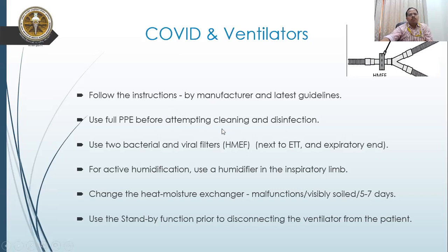Now, if you are attempting any cleaning or disinfection of these equipments, use full PPE. PPE stands for personal protective equipment, so that you yourself are prevented from getting the infection. Third point is use two filters, the disposable filters which I was showing you in the first picture. There are two types. You need to use two filters. One at the Y-piece and the endotracheal tube, and the other one at the expiratory port of the ventilator.